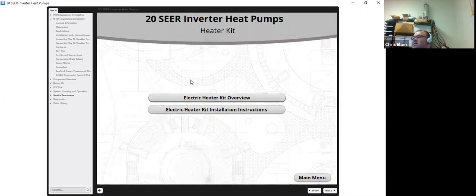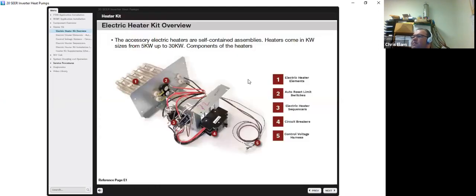Going to the heater kit. The accessory electric heaters are self-contained assemblies. Heaters come in kilowatts from 5 up to 30 kilowatts. They're accessories. They do not come on the air handlers. So you basically have a couple components to these heater kits. One, you have your electrical elements. Two, you have your auto resetting limits. Three, you have your electrical sequencers. Four, you have your circuit breakers. And then five, you have your control voltage harness.